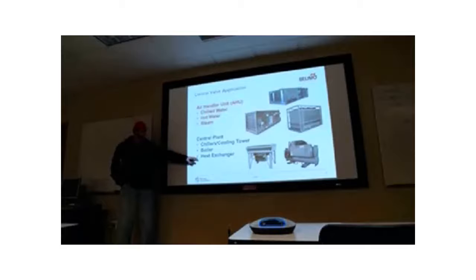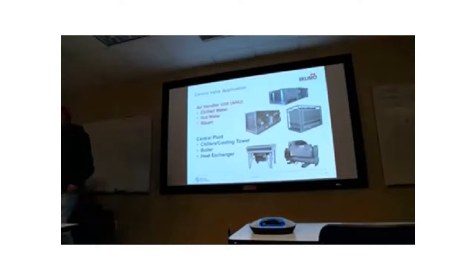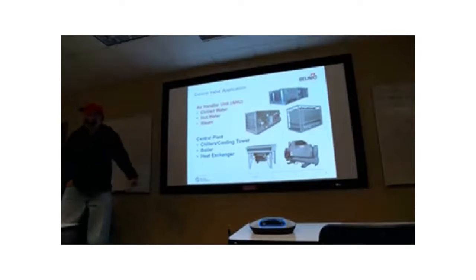Has anybody worked on what they call a water side economizer? Somebody's laughing. What's that? Never work on that. Well, what they do is they just save energy, because you can use the tower water as a heat exchanger. You can run it through a heat exchanger.